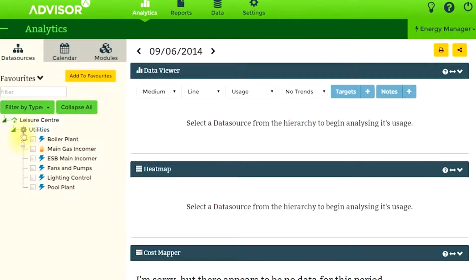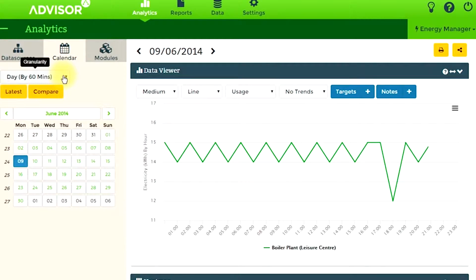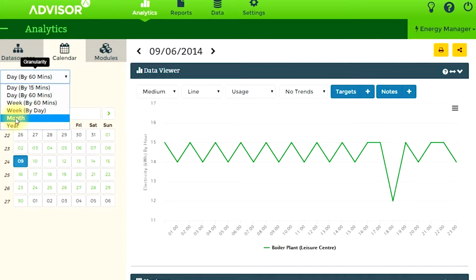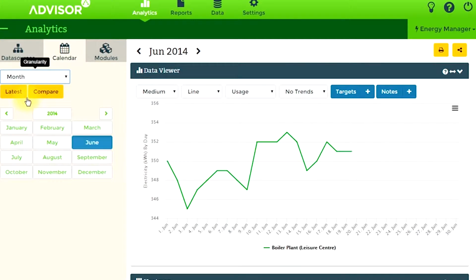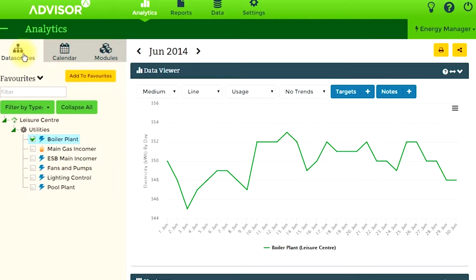Now let's talk about the overall heating and boiler system. Before we came, this site was not using a combined heat and power, CHP, system. Using both monthly view and daily 15-minute view on Advisor, we were able to see that the CHP system will be of major benefit due to constant demand for both electricity and heat.